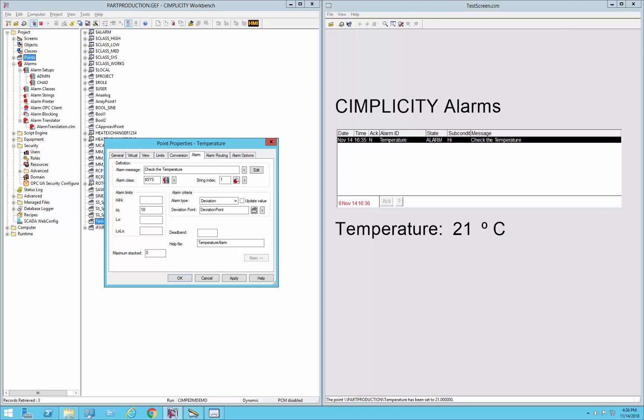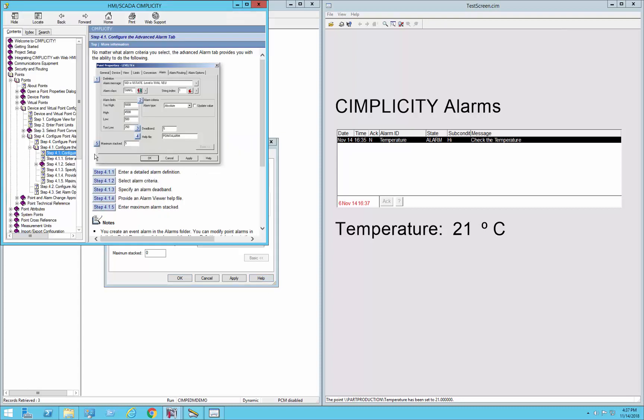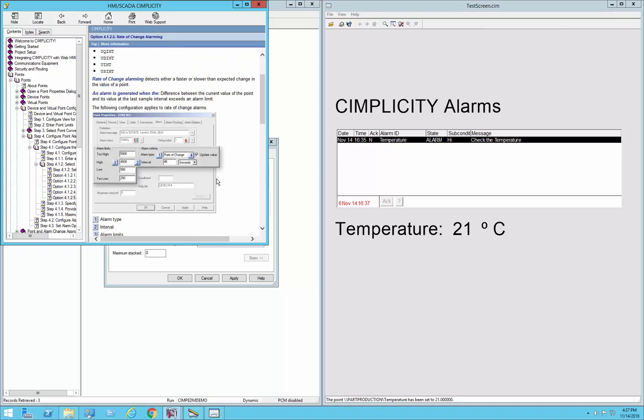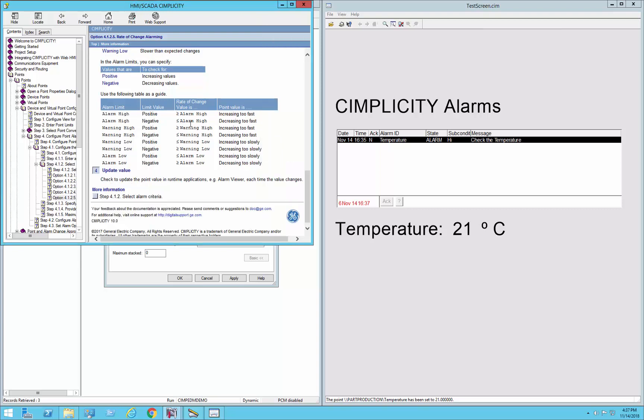Finally, we'll talk about probably the most, maybe the most complex type of alarm, which is rate of change alarm. So if you look at, when you switch to rate of change, it gives you a new field called interval. If you look at the tool tip, you'll see that this indicates how often I should check to see if the value has changed more than an alarm limit. So I would suggest that you go to the help, and go to the alarm criteria, rate of change alarm. It gives you a good table showing you how to, how it detects rate of change.